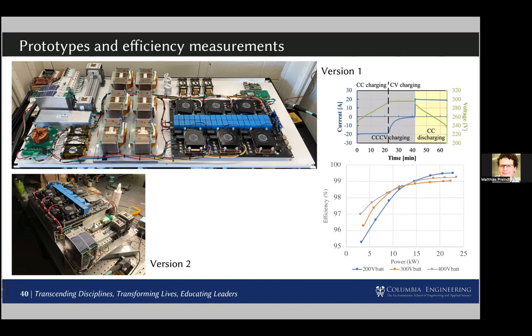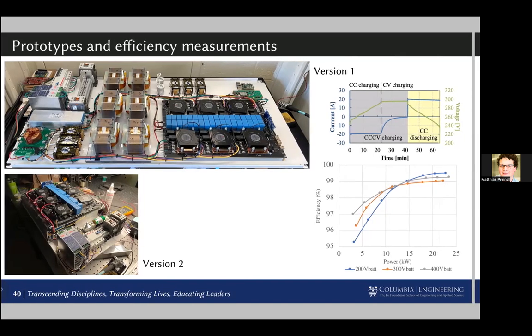The efficiency, so you can see there's an example of the charging behavior. These are experimental measurements, actually. There's constant voltage, constant current charging to charge a battery, and the efficiency ranges, at the lower voltage and lower power end, from 95-96% up to 99% plus at the higher power levels.